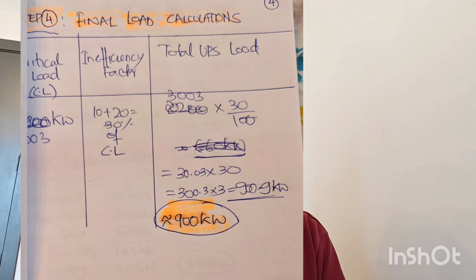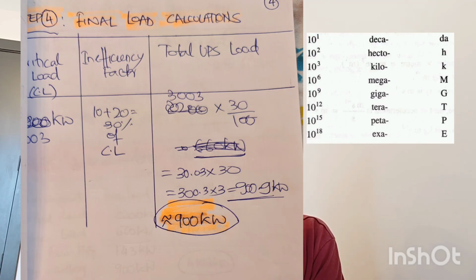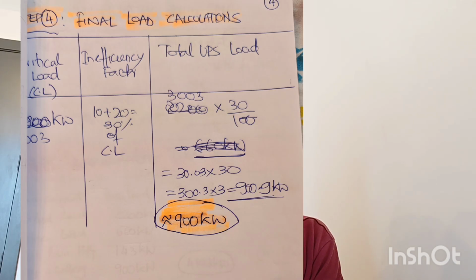Now, step 4, the final load calculations. So here you have the critical load, that was 3003 kilowatt or 3.003 megawatt. Mega is 10 raised to 6, kilo is 10 raised to 3, just for those who don't know. The inefficiency factor we calculated, 10 plus 20, is 30% of the critical load. So that gave us 3003. That is the final load, actually. 3003 times 30 by 100, 30%. And you have a total of 900.9 kilowatt. That is 900 kilowatt or 0.9 megawatt. Okay, so that's the final load.